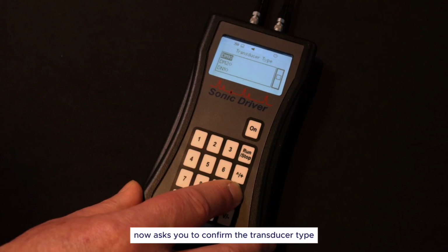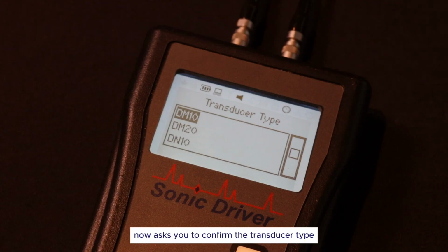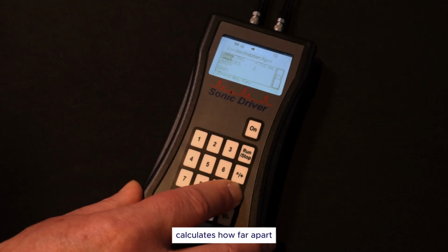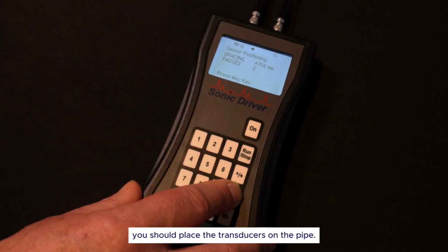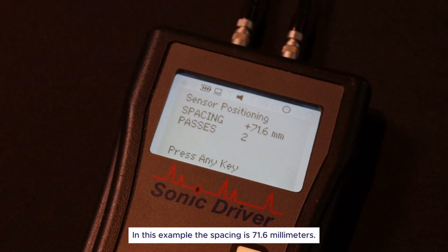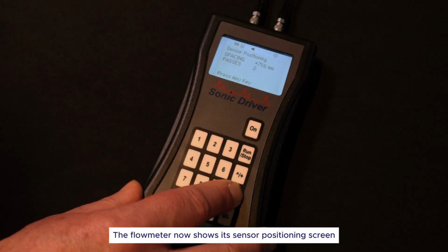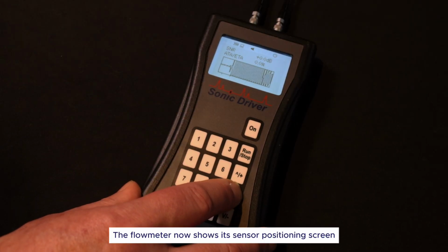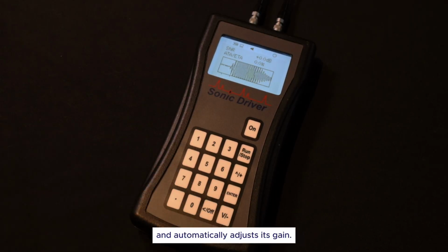The flow meter now asks you to confirm the transducer type, and based on the values that you have just entered, calculates how far apart you should place the transducers on the pipe. In this example, the spacing is 71.6 millimeters. The flow meter now shows its sensor positioning screen and automatically adjusts its gain.